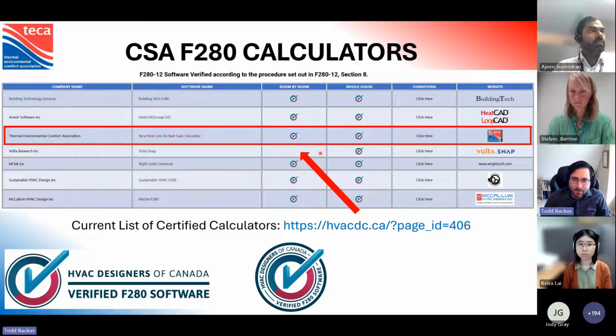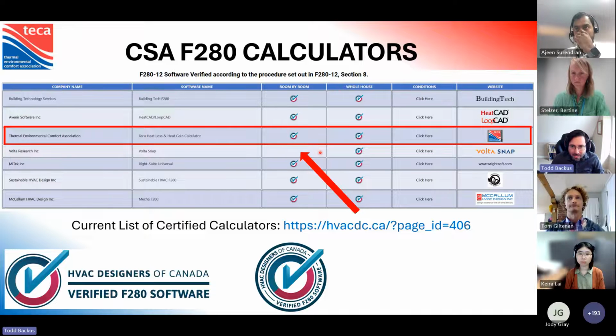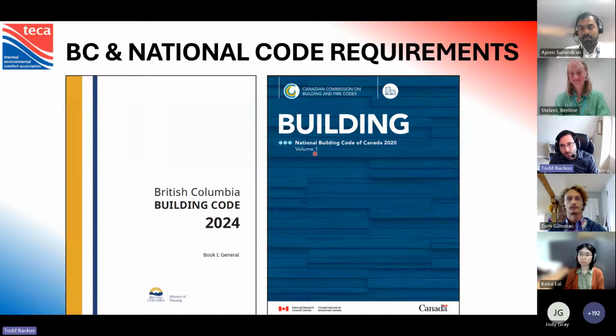Another one to be aware of is Volta Snap. It's very popular, especially among EAs, but be mindful that Volta Snap is really for the whole house. They do what's called a block load, where they will examine the entire dwelling. They will not look at a room by room calculation. Now, as a contractor and as a designer, I feel it is your responsibility to provide a room by room calculation in order to understand how this system should be divided. Because if you do a block load, you'll know roughly the size of the equipment that you need, but how much heating do you need in the living room? How much do you need in the primary bedroom? You will be essentially guessing if you have not completed a room by room calculation. So as a contractor, I feel it is your obligation to provide this, even if the EA has provided a block load. So moving on to the code requirements.